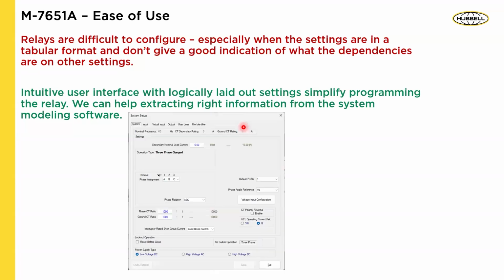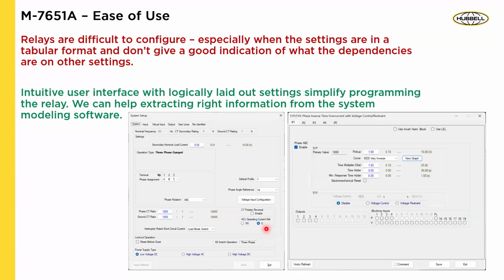So as you see here on the system setup, you have your system, your input, virtual input, output, user lines, file identifier, and then here's your terminal assignment, your phase rotation. Here's your CT ratios, right? Here's your CT polarity, right? So we make it very easy and logical for you to follow through.